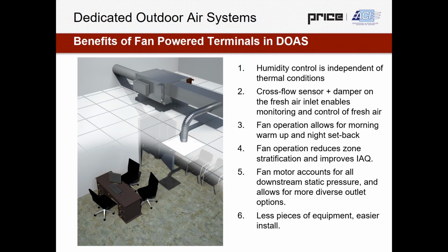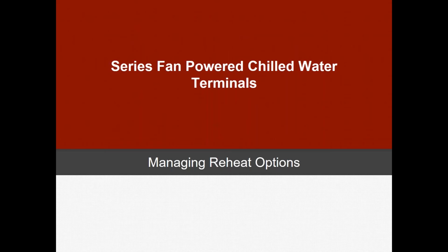And then last, there's also less equipment and it's easier to install. So for instance, when we look at comparing this equipment to chilled beams, the largest piece of equipment can essentially be consolidating maybe somewhere between 30 and 40 linear feet of 24-inch active chilled beam. So what that really means is just less equipment to install and maintain within the space.